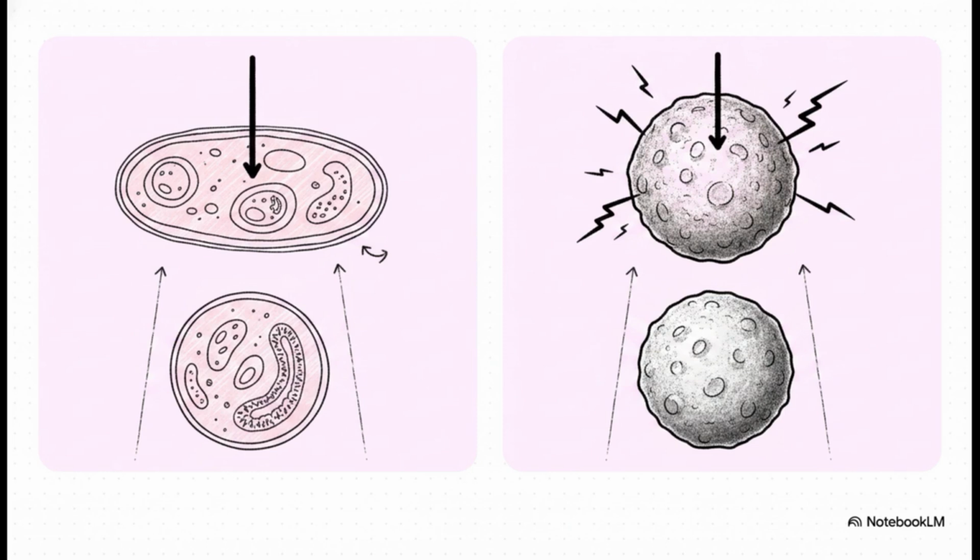Well, we generally split this incredible technology into two distinct methods. You've got transmission electron microscopes, or TEM, and scanning electron microscopes, or SEM. With TEM, the electron beam is fired directly through the specimen, which gives us a highly detailed 2D view of internal structures. SEM, on the other hand, fires the beam onto the specimen and it bounces off. It reflects. The scanning method gives us stunning 3D images of surface structures, though it is at a slightly lower resolution compared to TEM.